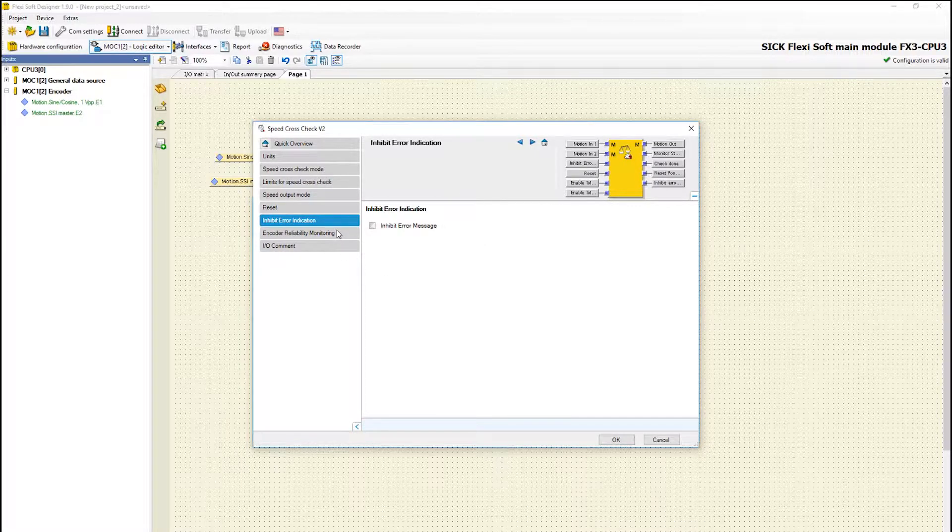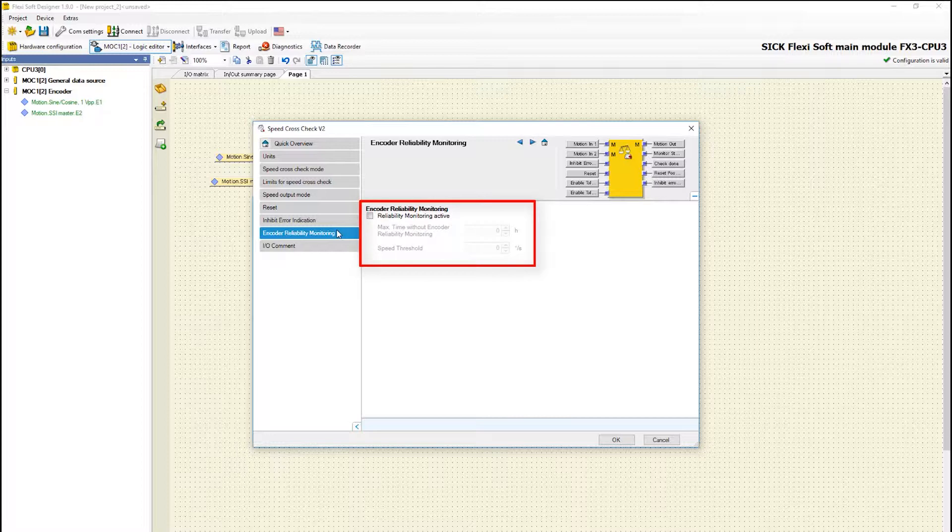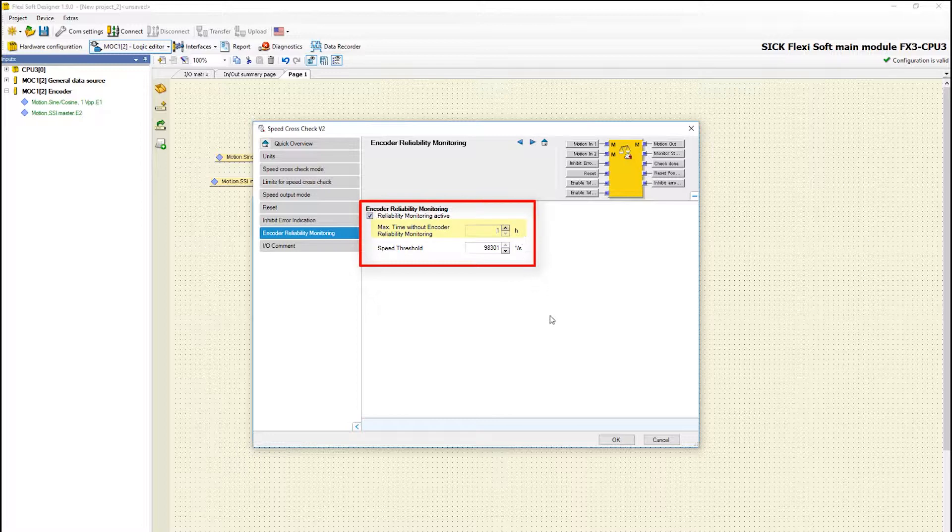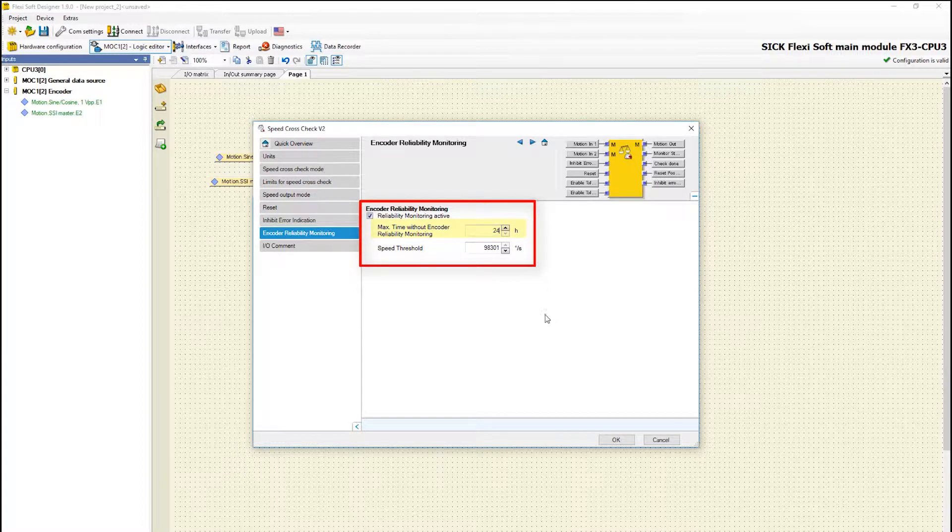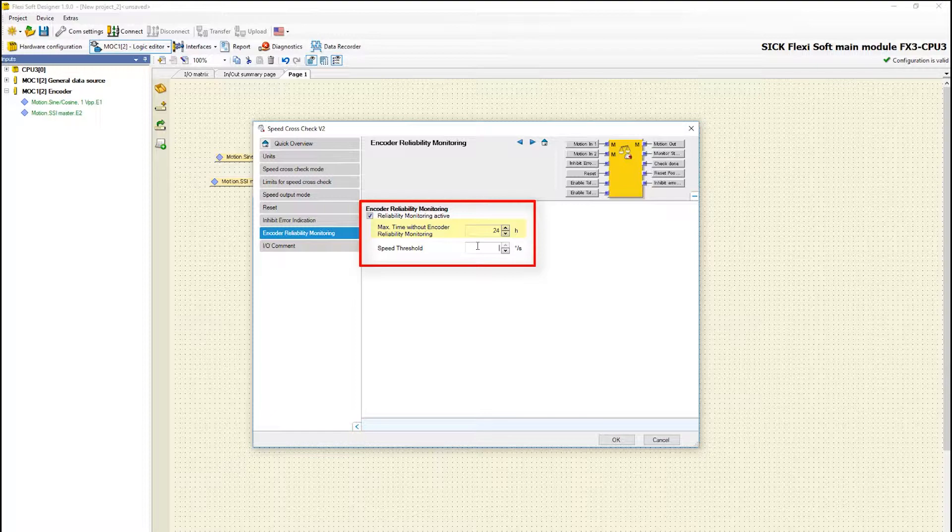And the last tab encoder reliability monitor enables a check to establish whether the signals of the encoders were reliable or not, for example because of damage during standstill. To make sure that the encoder signals are still reliable the motion in speed needs to cross the defined speed threshold minimums once during a max time interval.